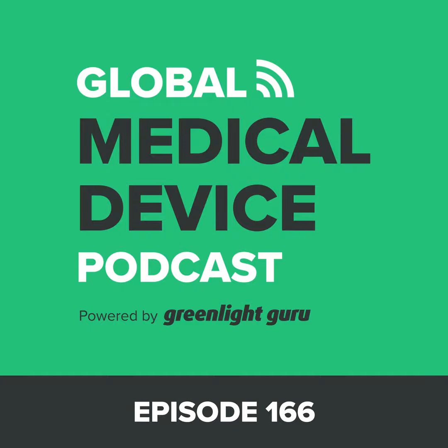So specifically, there were three either new or updated guidances that FDA has put out literally within the last month. And let me just tick them off very quickly, and then we can talk about them individually. The first one, and really the only new one, is titled Select Updates for Biocompatibility of Certain Devices in Contact with Intact Skin. And that was a draft guidance that just came out literally a week or two ago.